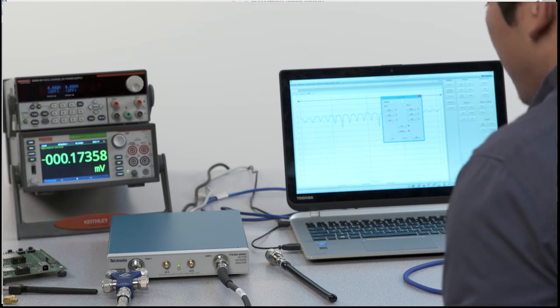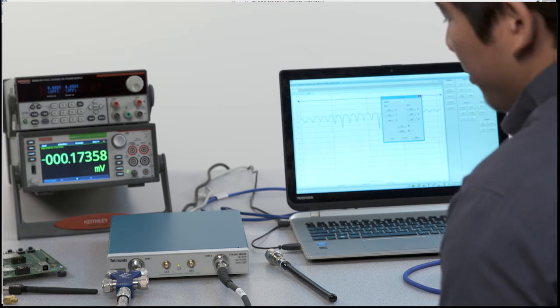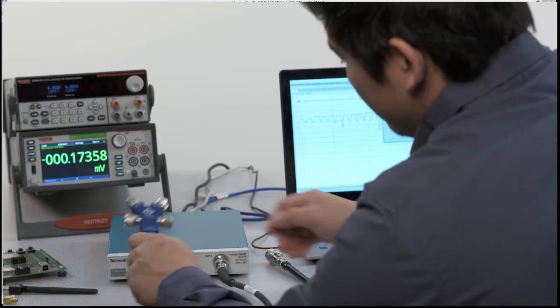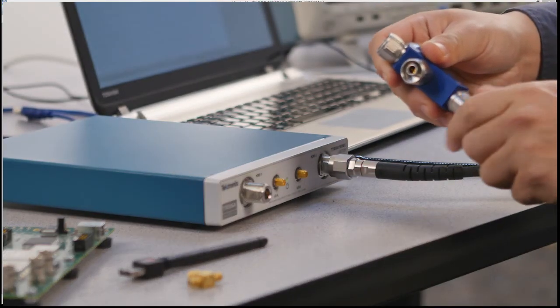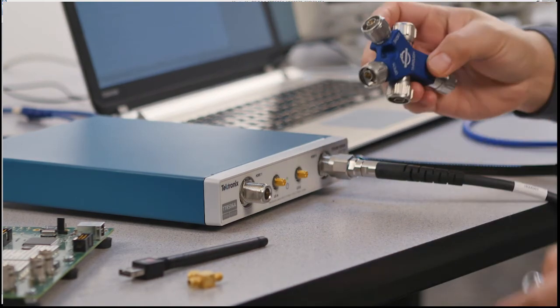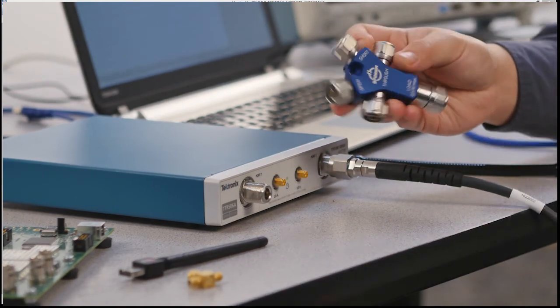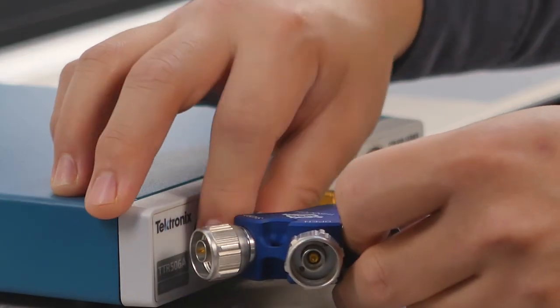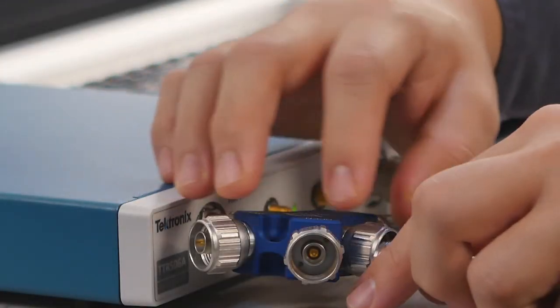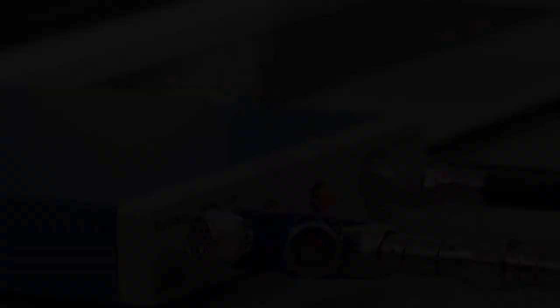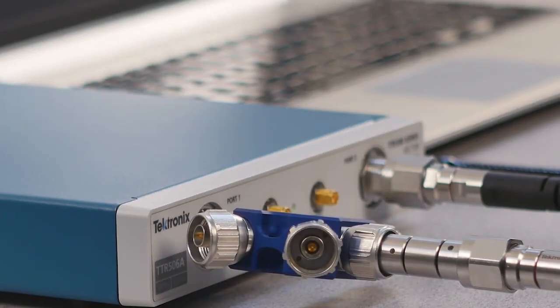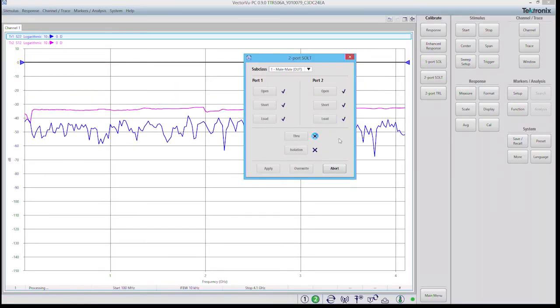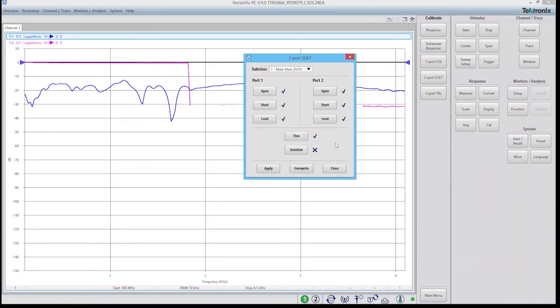Now that both ports have been completely OSL calibrated we're going to need to do a through calibration. So I'm going to disconnect the cal kit and I'm going to use the through to connect from port 1 directly into port 2. There I click through and then click apply.